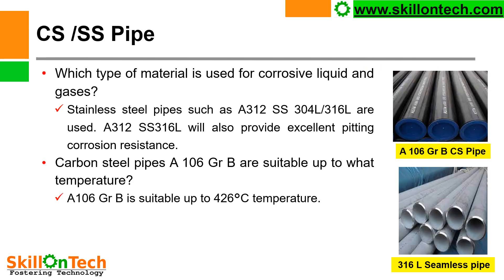CS (carbon steel) and SS (stainless steel) pipes — you can see a picture of A106 grade B carbon steel pipe and a picture of 316L seamless pipe. 316L is a low-carbon stainless steel pipe. For corrosive liquids and gases, stainless steel pipes are used, such as A312 SS-304L and 316L. A312 SS-316L also provides excellent pitting corrosion resistance. Carbon steel A106 grade B pipes are suitable up to 426°C temperature.